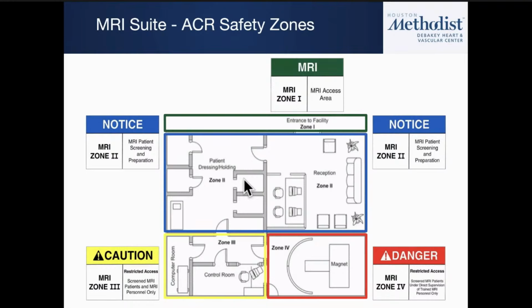Nowadays, most orthopedic implants are generally made of a material that's not ferromagnetic, meaning it doesn't get pulled toward a magnetic field. It may cause an artifact in the image, but it won't be pulled. With things like pacemakers and defibrillators, you may need to reprogram the device before you take the patient into the MRI scanner. So there's an extensive amount of screening that happens in zone 2. Zone 2 is essentially a mixture of people who have completed MRI screening, as well as people who are in the process of getting their screening. The reception area would be considered zone 2, as well as the patient holding and dressing area.